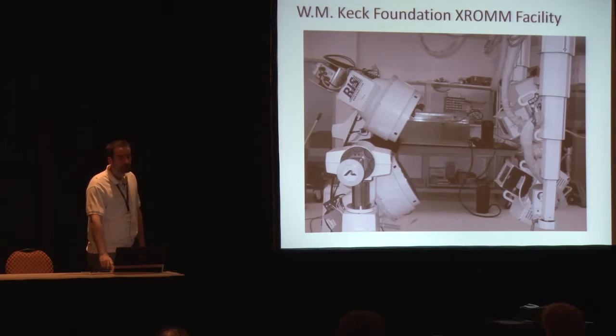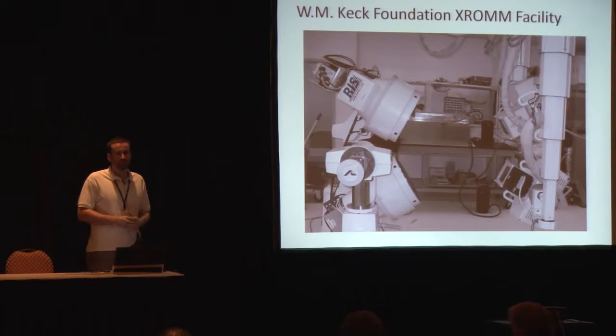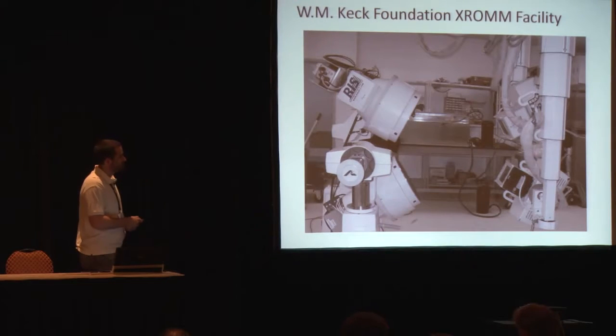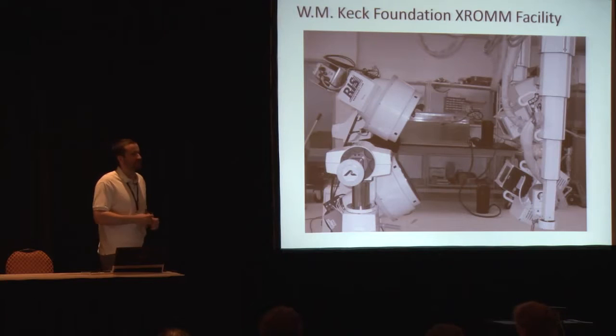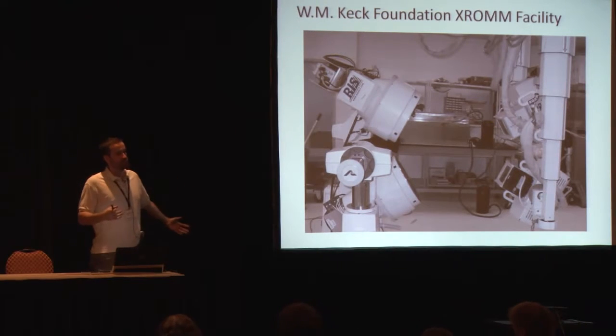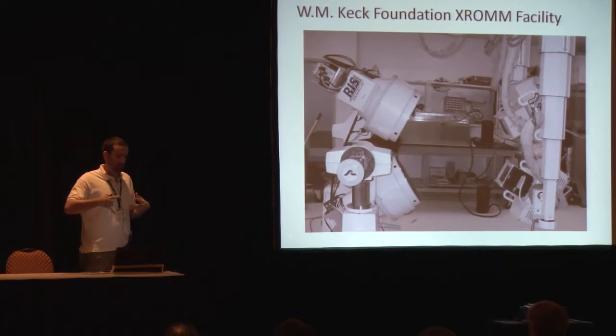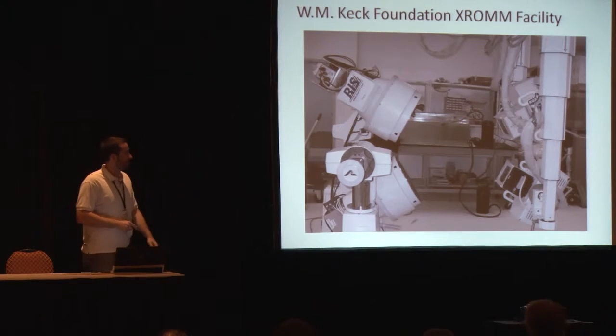Sure. Now, you asked whether you can use the X-ray sources like this to get stereo views. So the question is whether we could set them up close enough to each other that we could get 3D stereo views. That's an interesting question. I'm not sure. There's still a limit to how close you can get these because of the housing. Now that we have a separate sled with the image intensifier, we have lead irises that we can open and close so that we're not shooting X-rays off of the intensifier. So there's that housing, the tilt housing and things like that.